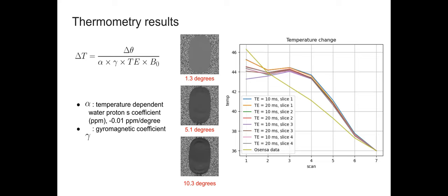Using the scan data at the lowest temperature as reference, we can see that a larger temperature difference between the two scans yield a larger phase difference, as shown in the middle column. Eventually, we plotted the estimated temperature at all slices and all echo times and plotted them against the Osensa data.